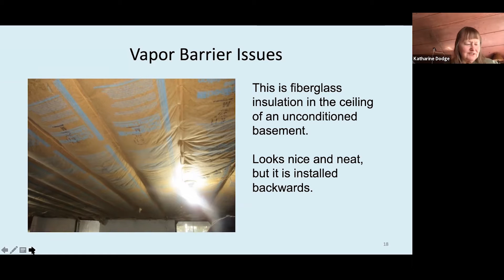In this picture, there's something wrong. It should be part of a moisture control strategy for homes, and that barrier should always face the conditioned space. They installed this fiberglass insulation incorrectly - it should be flipped over, with that paper up against the plywood decking of the first floor. That's something we found in a lot of homes we were assessing, that they did it backwards. It looks neat, and it just made sense to not have all that fiberglass showing, but it was backwards.